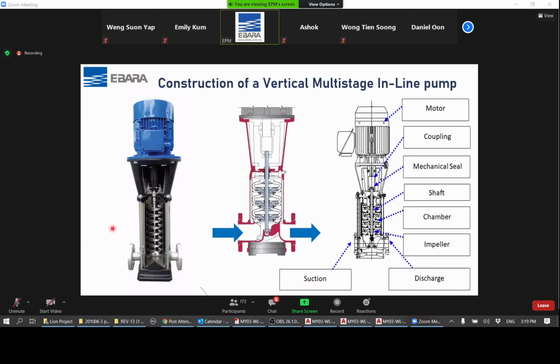So if you can see from the picture here and a drawing here, in this drawing there are 3 stages or 3 impellers. So the water will come in from here and it will be channeled to the first impeller, or we call it the first stage, and this impeller, when it's rotating at the speed of the motor, usually we call it 3000 RPM or 2900 RPM, it will actually impart a centrifugal force to the water, and that water will be channeled to the second stage.